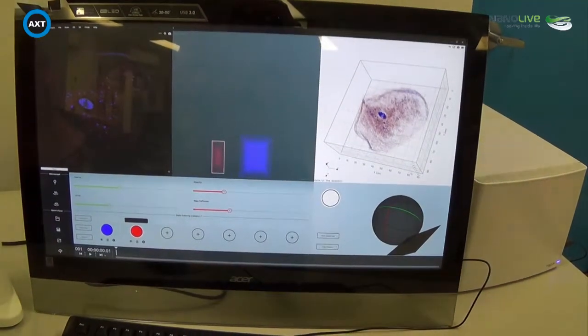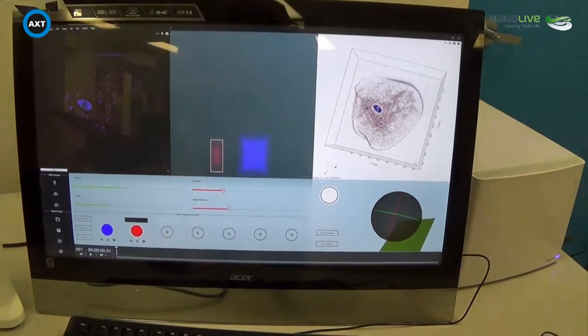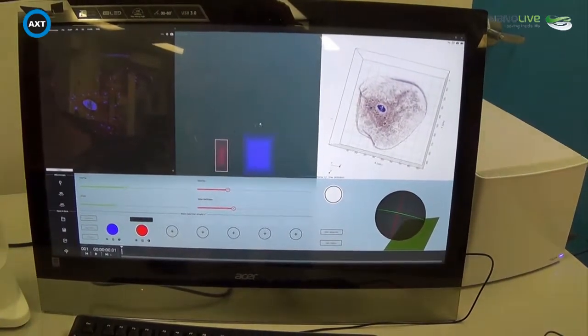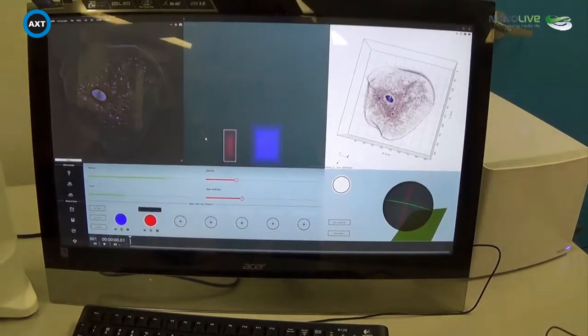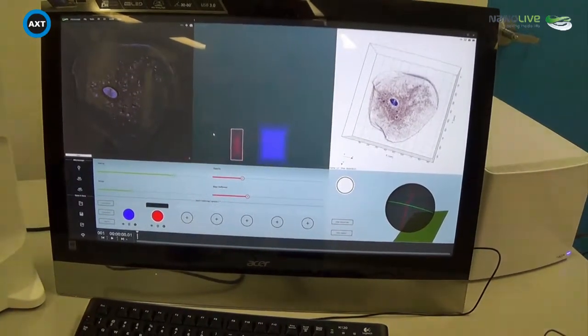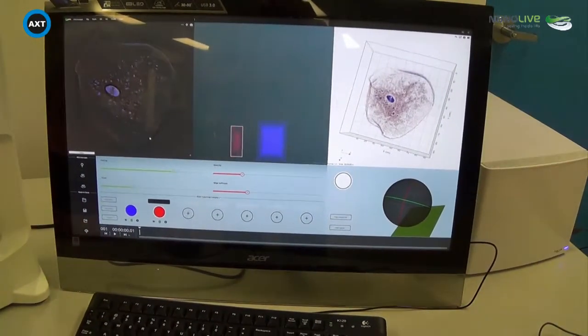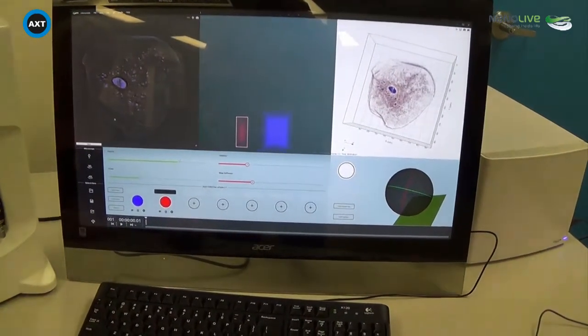And so what's the maximum size cell that you can view with the 3D Cell Explorer? So your maximum thickness of cell that we can image is 30 microns in the Z direction. So if you have cells that you have adhered to a plate and they have stuck down, they'll tend to flatten out a little.